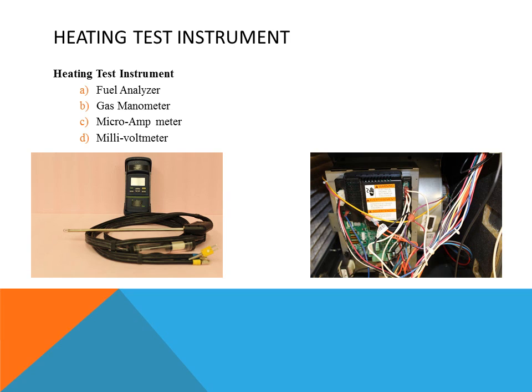The fuel analyzer can also tell you how much excess air the burner is consuming and the discharge temperature of the flue gases — to see if it's in the correct range. These are tools used to help troubleshoot and adjust the system to the ultimate efficiency percentages. There are also microamp meters, which are used to check DC current flow through the flame rectification system to determine if it's in range and prevent the burners from locking out. Millivolt meters are used to check older systems, reading DC voltage from thermocouples to verify they are producing the correct output.